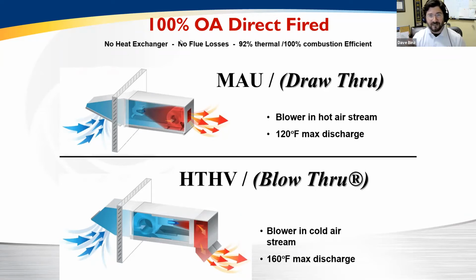But what HTHV does is move the blower upstream of the burner, where my mechanical components are now in the cold airstream. If I can get my burner to burn cleanly, effectively, and reliably at the high temperature, I can now put more heat into a smaller box, and that has demonstrable savings from an energy perspective and an installation cost perspective.